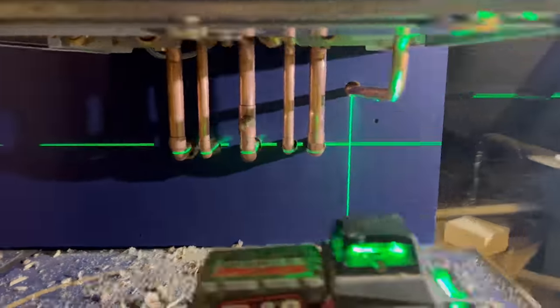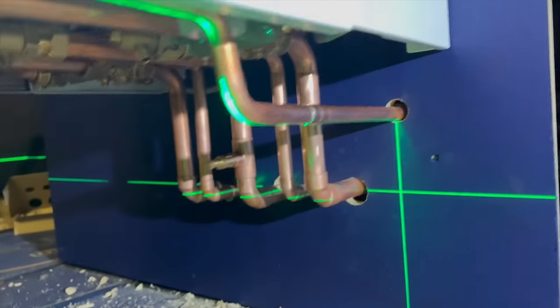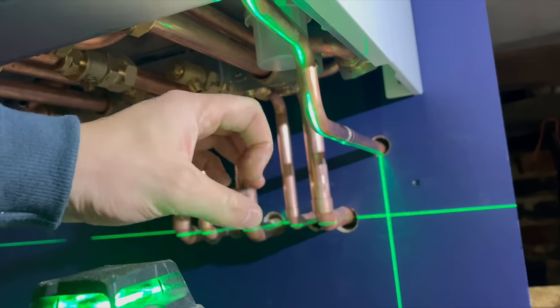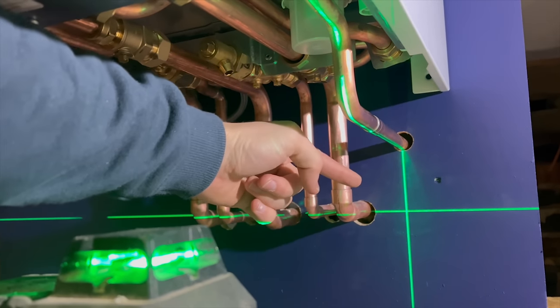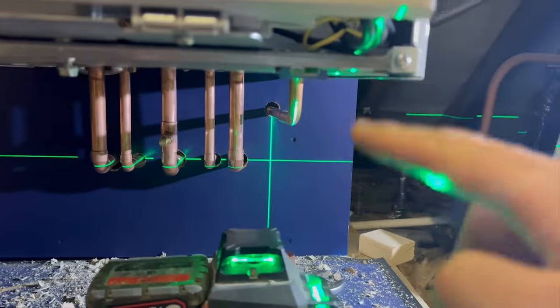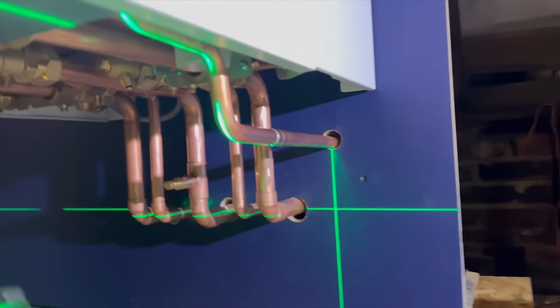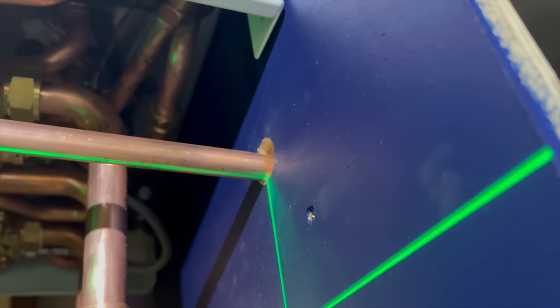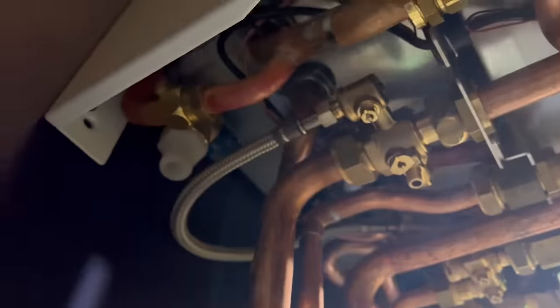I've got the pipes through there. There's nothing other than the gas nipple on this side and I've cut that with quite a distance off the wall. That's simply because I'm going to get my Armaflex insulation on — if there's a bit more of a return there, it just sits on the pipe a lot more nicely. We have the advantage of doing all the plumbing behind, so when you're looking at it, it will just look clean — black insulation going through, black condense, all lovely, with just the gas nipple exposed. One of the benefits is that if anyone does maintenance, there's a PRV at the back there — just having that little gap behind the pipework gives you a bit more room to get tools in.